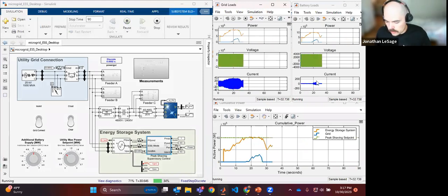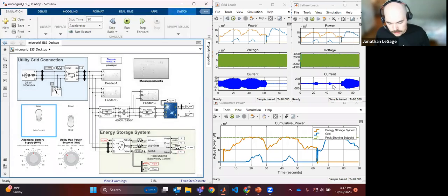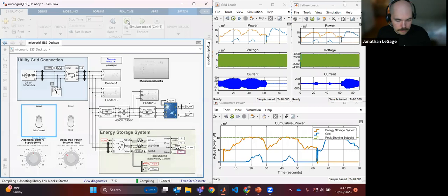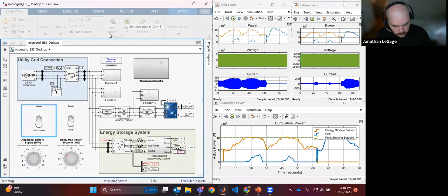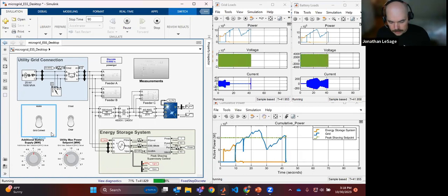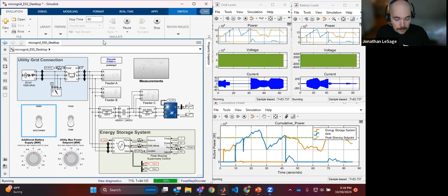Right now it's in peak shaving mode — once local demand on this feeder exceeds a certain point, the energy storage system kicks on. I'll now issue a command to island this microgrid, and you'll see that the battery current shows we're doing grid forming with this energy storage system as a local microgrid. Running it again, I'll throw the island command a little earlier so we can also see the resynchronization and reconnection.